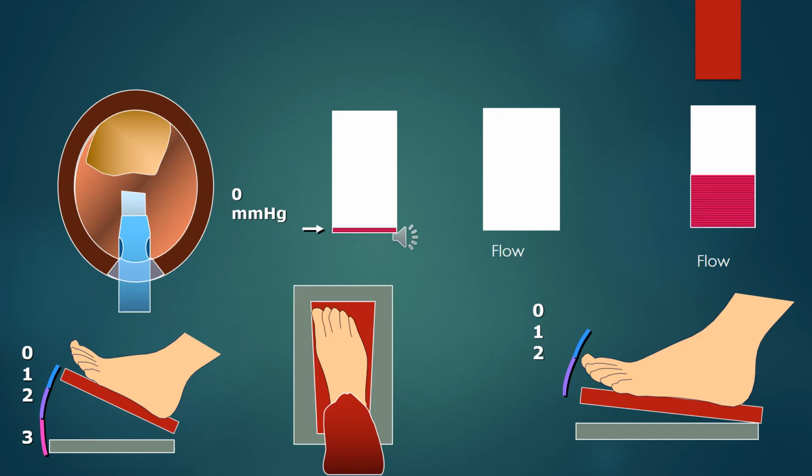How much will the vacuum generate here? Till your preset vacuum. So in this case, you have kept a preset vacuum of 400. So the pump will keep on rotating as long as the vacuum is not generated till 400. As the vacuum is generated till 400, you will find an occlusion tone. So in a phaco machine, you get that occlusion tone, beep, beep, beep. Different machines have different tones.